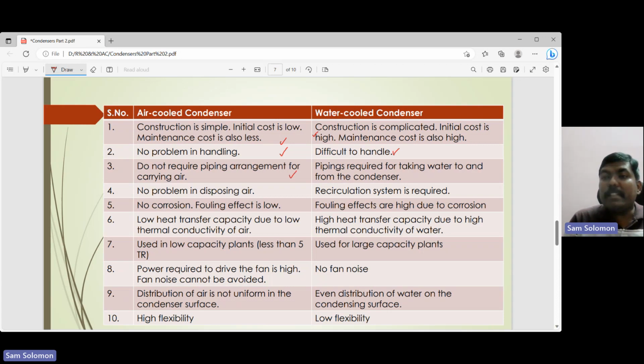Okay, and the air-cooled condenser doesn't require any piping arrangement for carrying air, because air, once it gets heated, tends to rise up very quickly. So you just need a fan to blow the air, whereas here you require piping to take water. Piping means additional material needs to be used, so that is going to add to your material cost. There is no problem in disposing air. Air can be taken in, and air can be rejected to the ambient. But here you need a recirculation system, you need a cooling tower, and then you need a pump to pump back to the condenser. So the recirculation system is required.